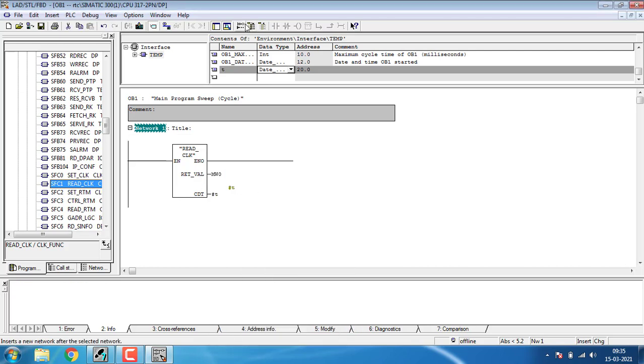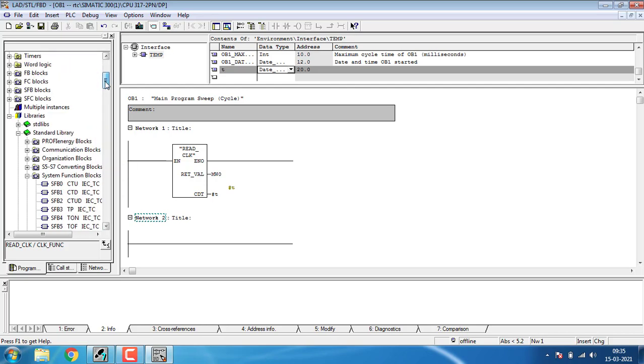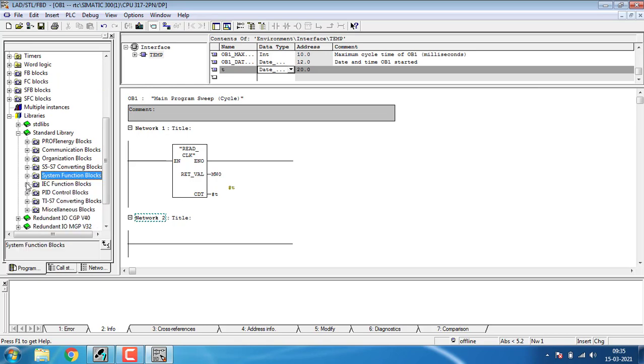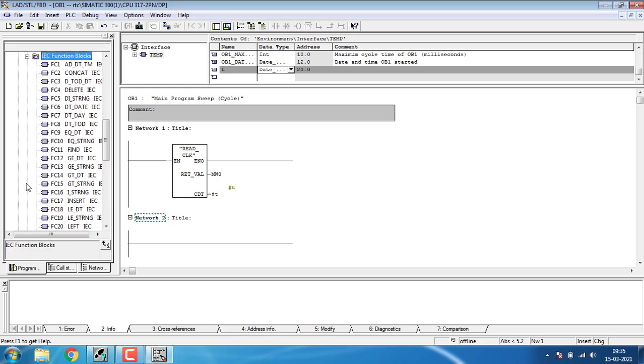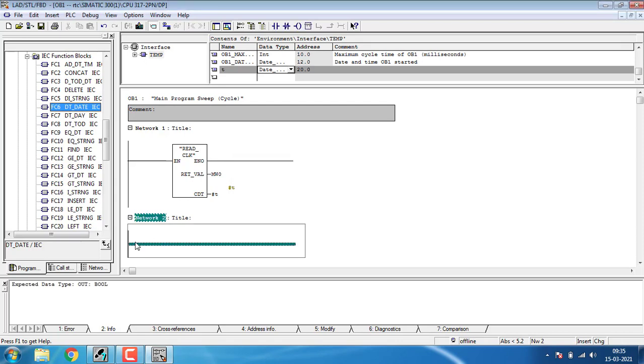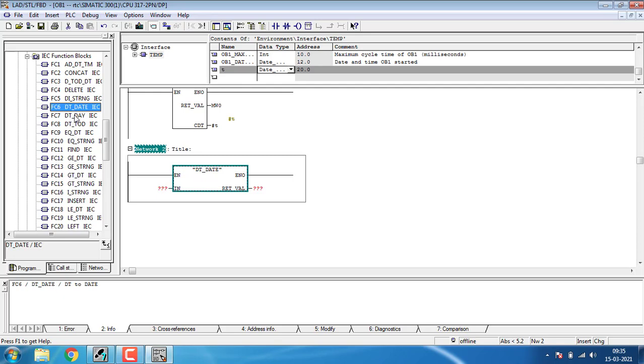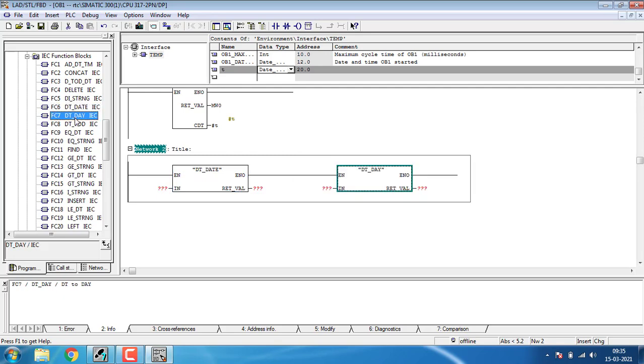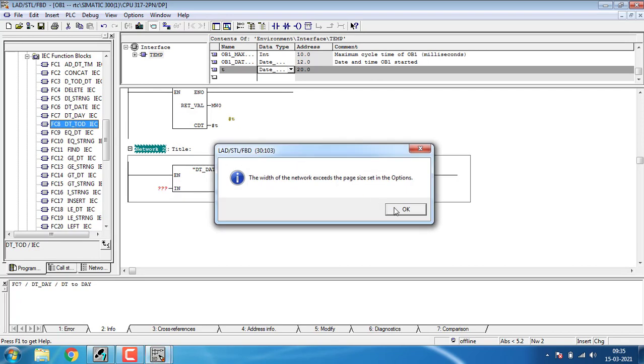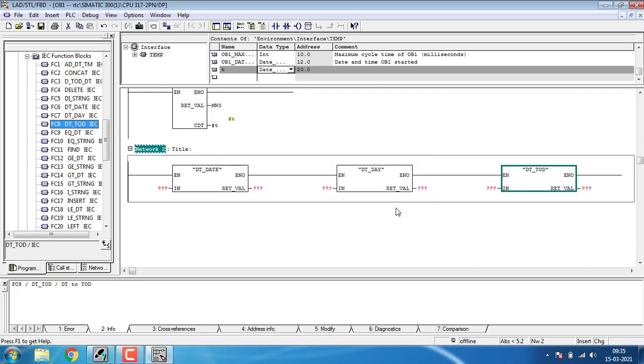I have to add one more network for adding some more function blocks. Close the system function blocks and go to the IEC function blocks. In the IEC function blocks, you can see FC 6 Date, FC 7 Day, and TOD which is the time. I'm going to place the function FC 6 Date, next to that will be Day, and next to that will be Time. All the functions have been placed.